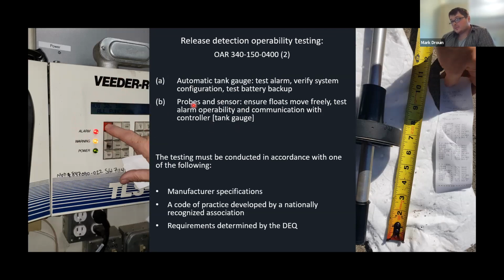Along with the tank gauge, we also want the probes and sensors tested. And this is a tank probe. This goes into the tank. It goes into the fuel, right? And this is a float. What we specify in the rules is that we want to make sure the floats move freely. So that's this part right here. We want to make sure that moves up and down freely and that it's clean. And then we want you to test the alarm operability and communication with the controller. That's how we word it. But basically, we want to make sure that this probe is programmed to communicate with this tank gauge. There's a bunch of different parameters that need to be included in there, but that's in general what we want done.